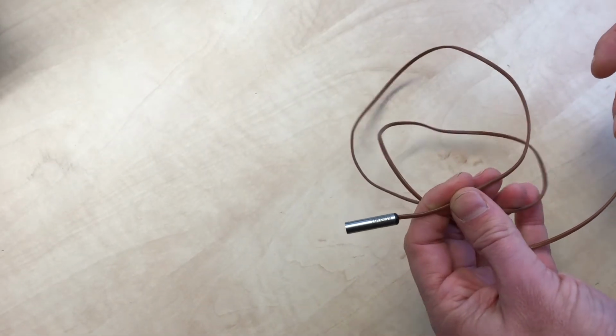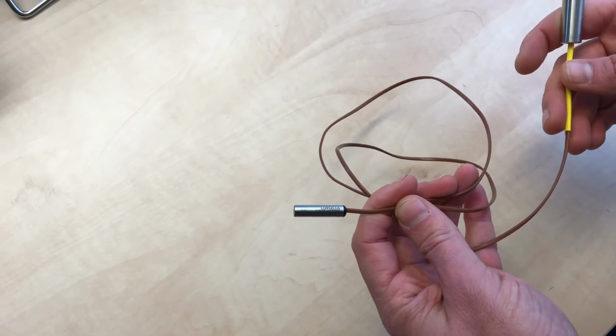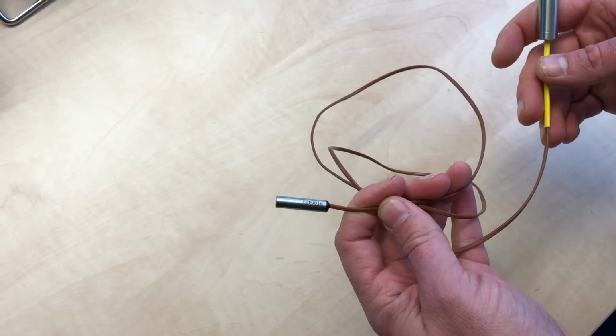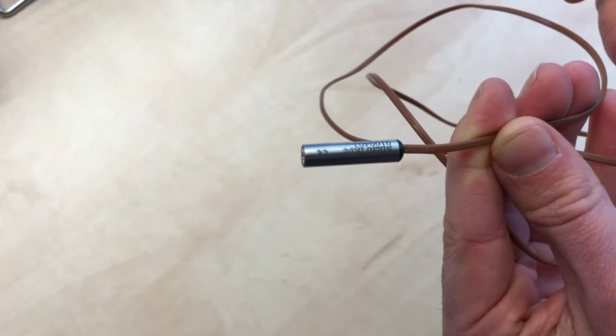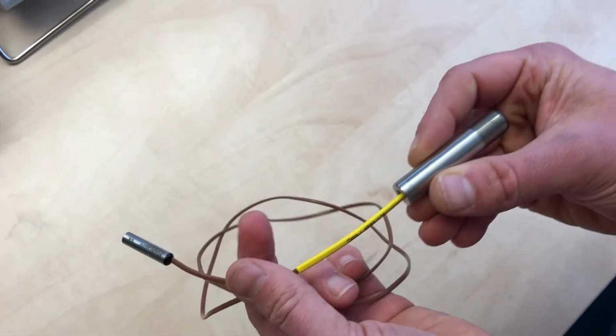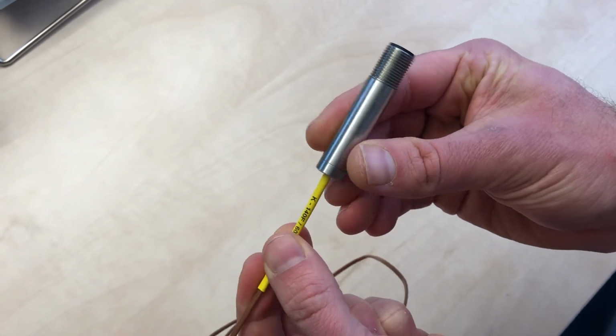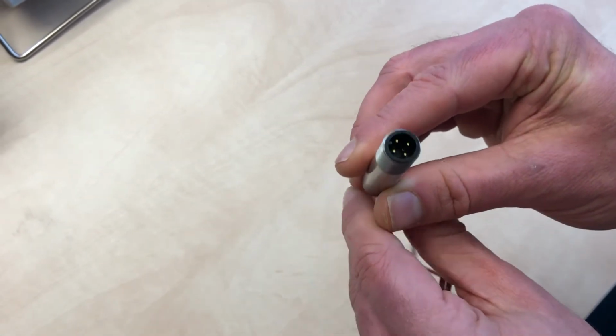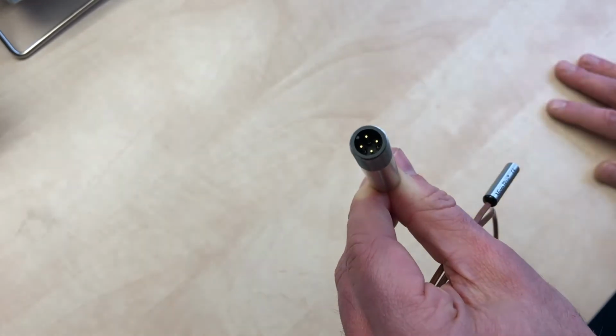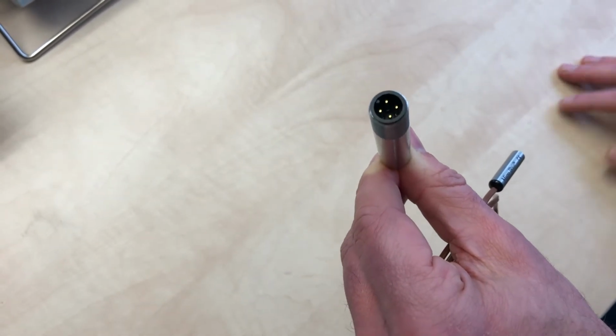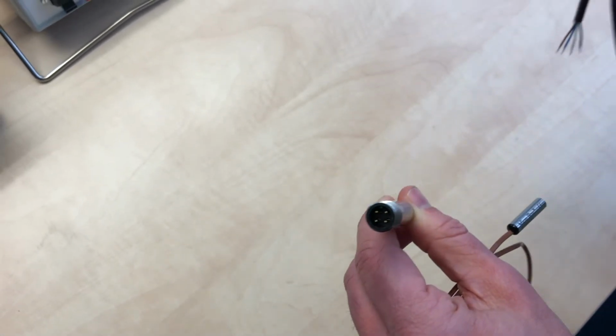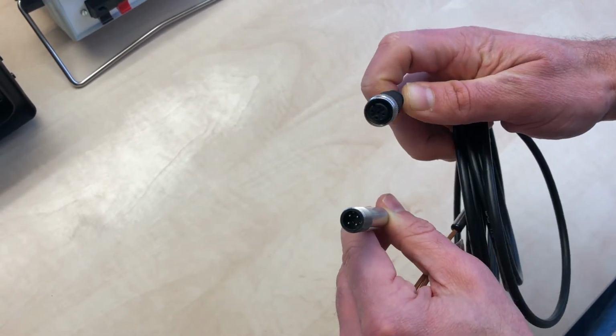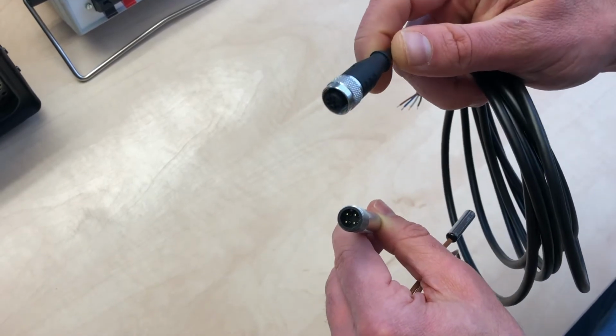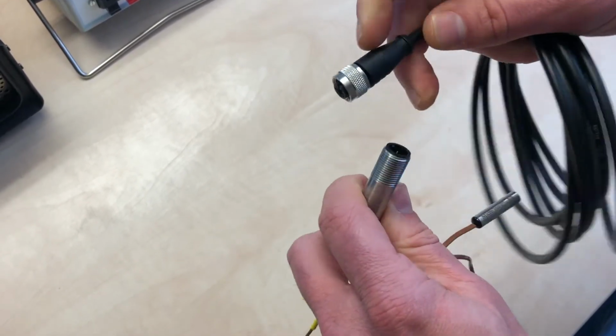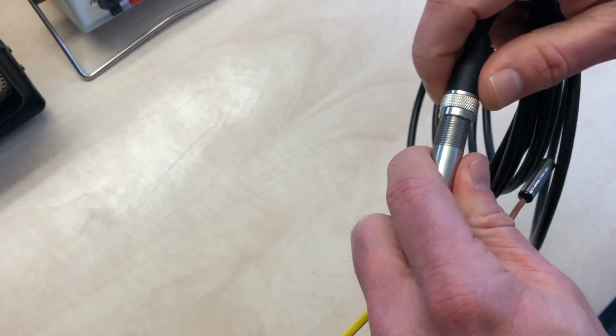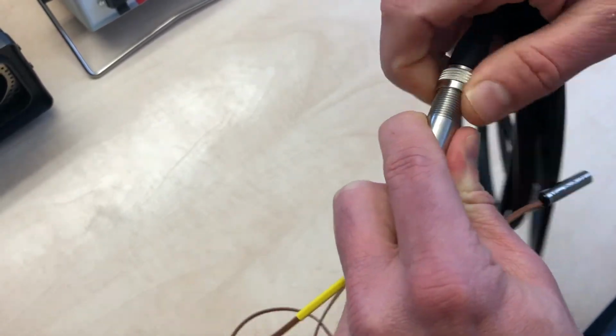As explained, you can connect several IRtc sensors to the AutoSmart transmitter. What you see here is the Micro IRtc, which is connected to the AutoSmart transmitter. In the back of the AutoSmart transmitter is an M12 connector. And with any AutoSmart sensor that you order, you will get a cable, of course with a fitting M12, that you can very easily connect to the AutoSmart.